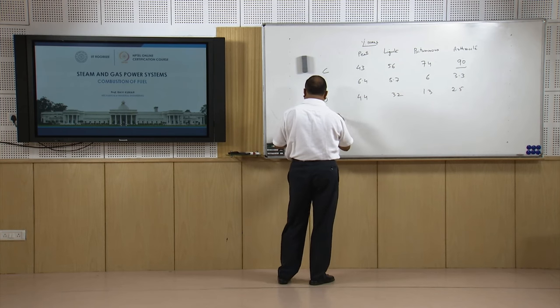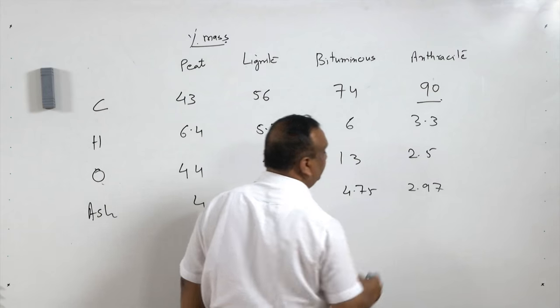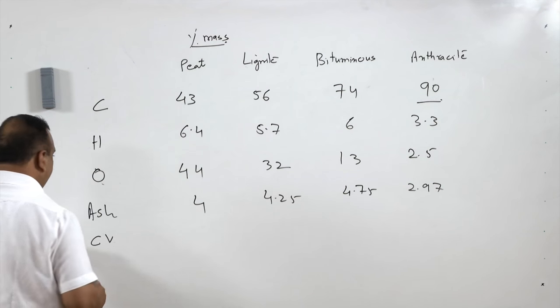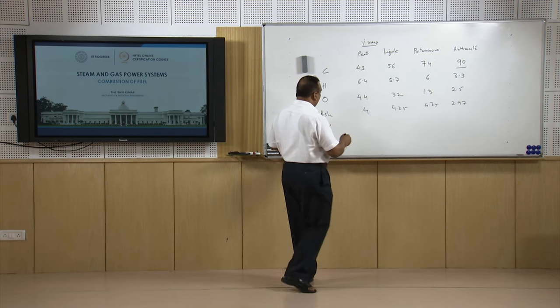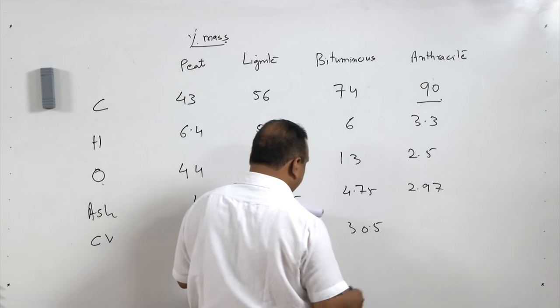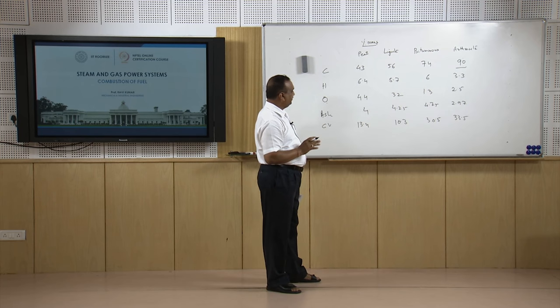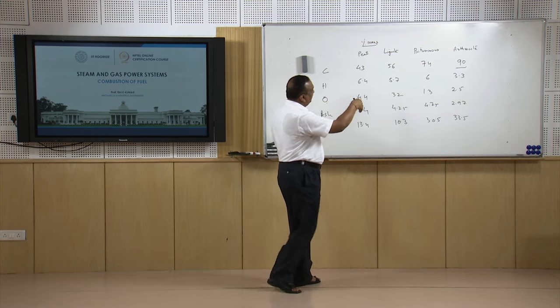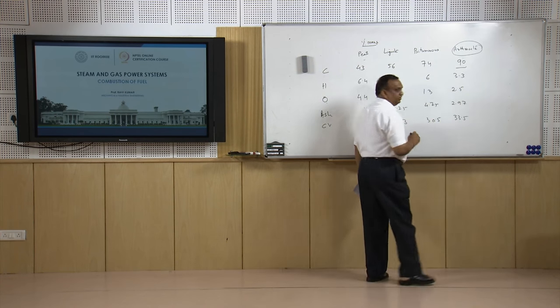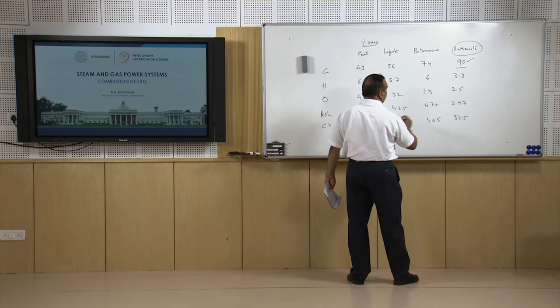Ash content: peat 4 percent, lignite 4.25, bituminous 4.75, and anthracite 2.97 percent. Calorific value of peat coal is 13.4 MJ/kg, lignite 10.3 MJ/kg, bituminous 30.5 MJ/kg, and anthracite 33.5 MJ/kg (approximate, can go up to 34). Anthracite is the best quality coal, with 90 percent carbon and ash content of only 2.97 percent.